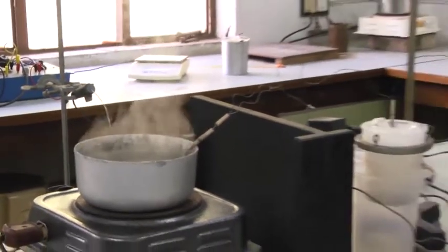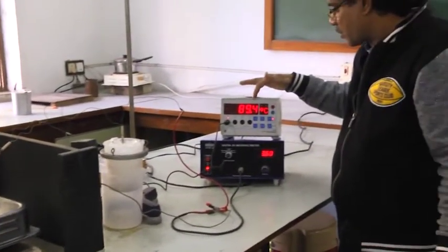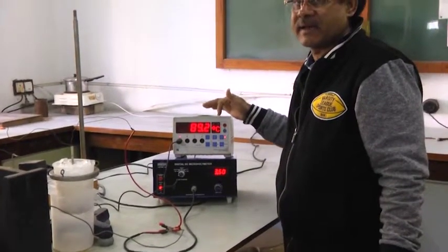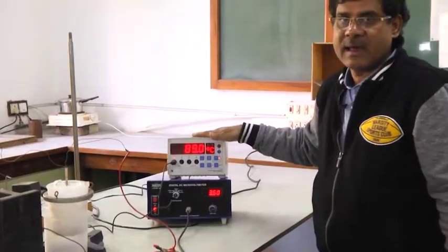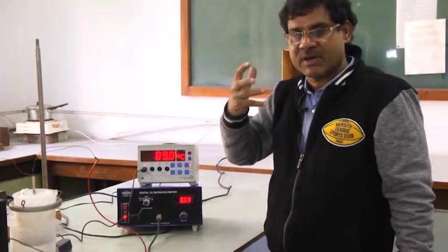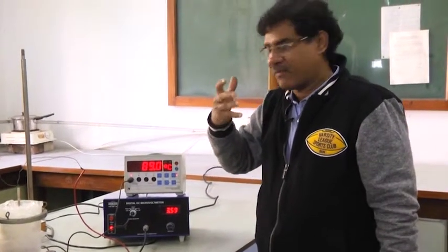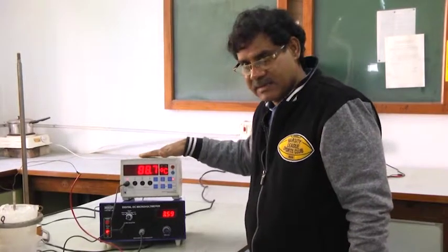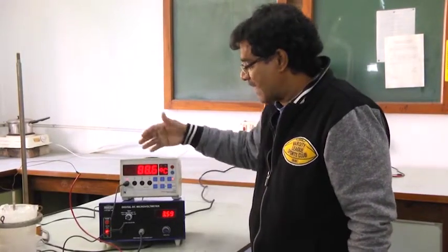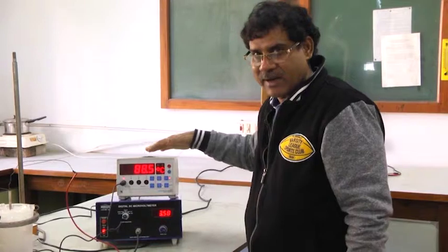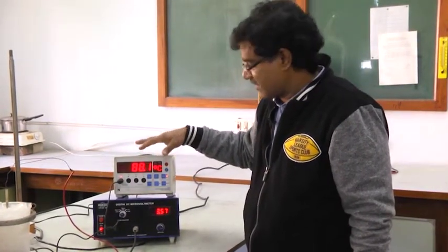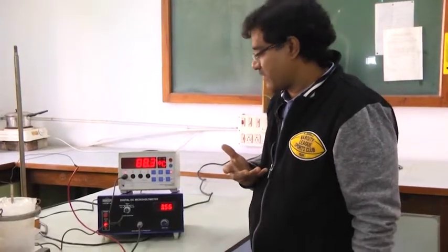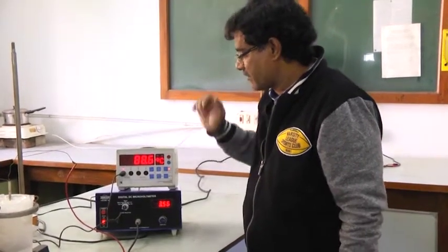So this meter is showing the temperature directly because this thermocouple is calibrated by the company, and that Seebeck coefficient, or calibration factor, is multiplied with the EMF electronically inside. So it then displays the temperature. Okay, it displays the temperature.